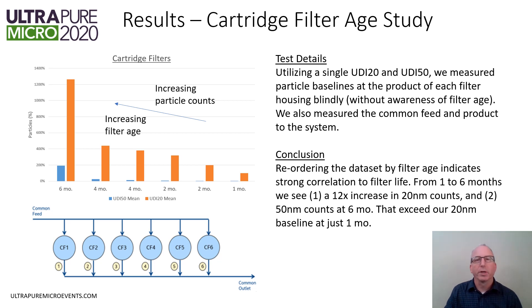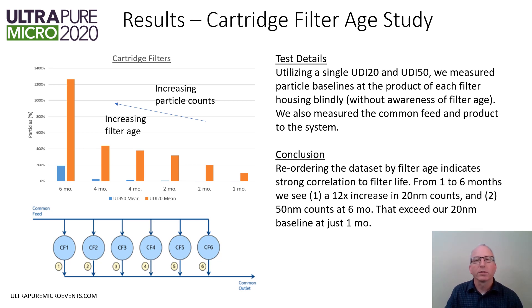As you can see from the schematic, our filter particle study was applied to an array of six parallel cartridge filter housings with a common feed and a common product. We utilized the UDI-20 and UDI-50 optical particle counters to measure particle baselines on the product side of each filter housing, as well as on the common feed and common product. Reordering the dataset by filter age exposed a strong correlation between particle counts and filter life. Remarkably, from just one to six months, we see a 12x increase in 20 nanometer counts, and 50 nanometer counts at six months will exceed our 20 nanometer baseline at just one month.